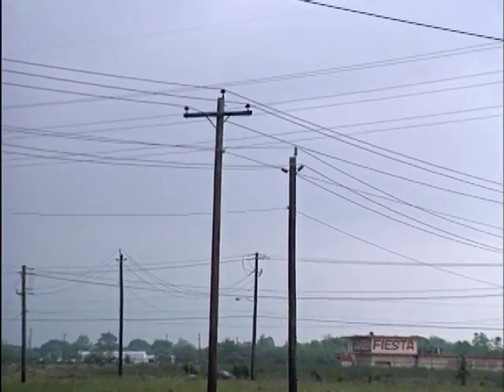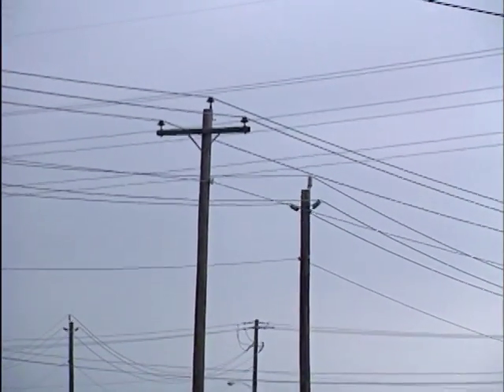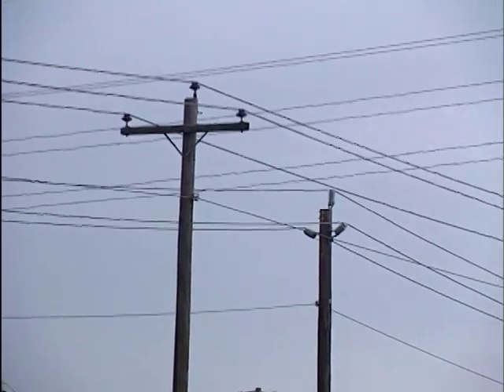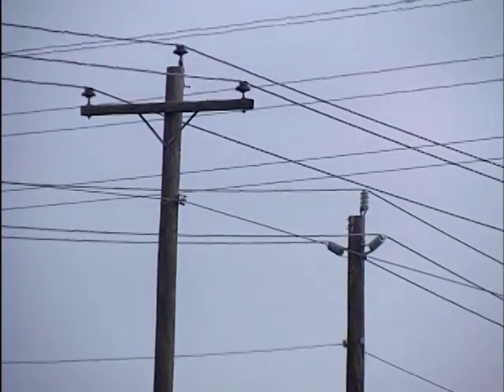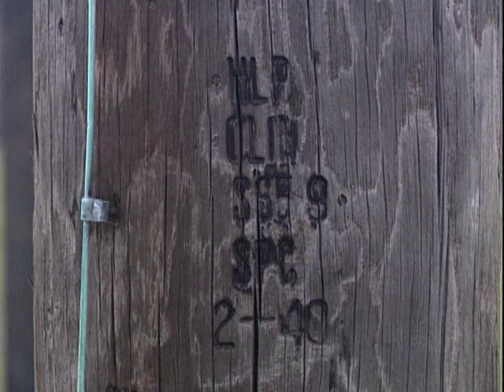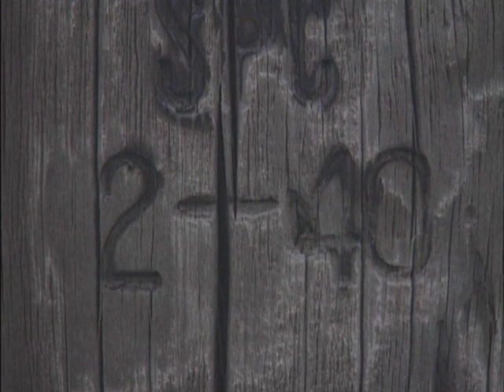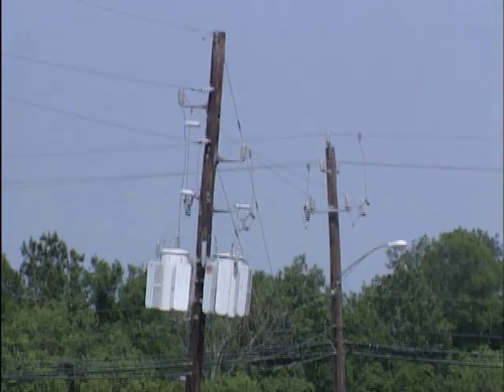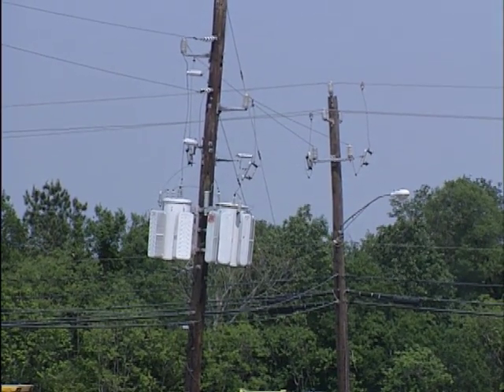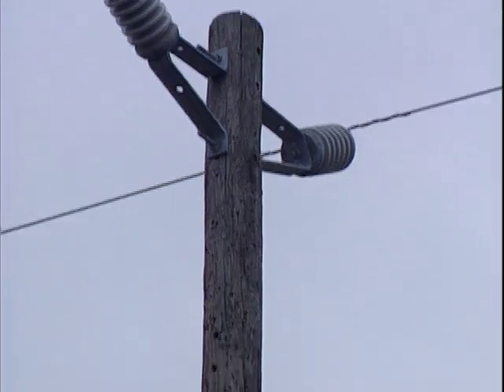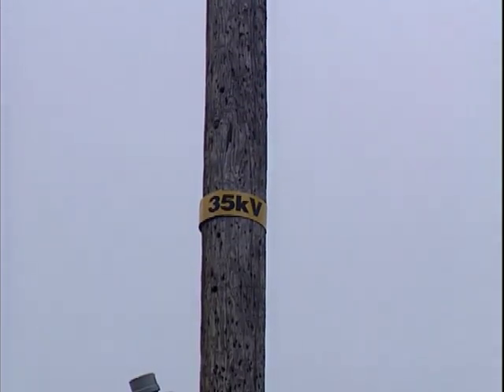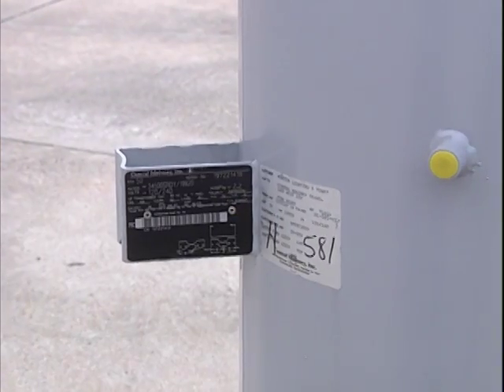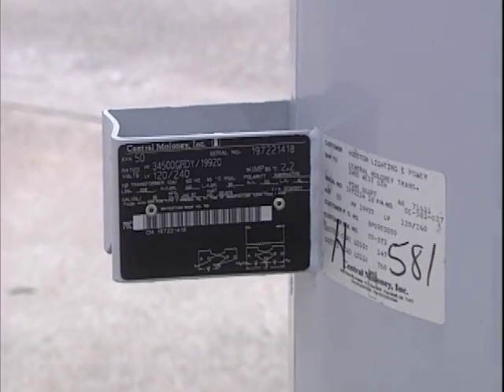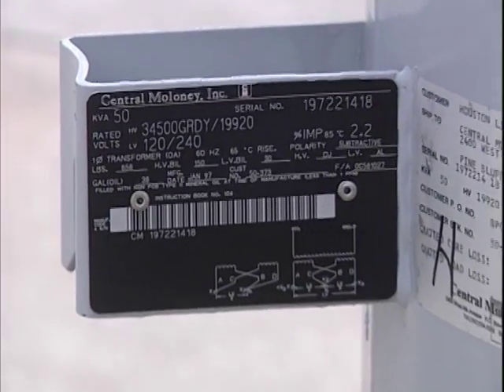The 12 kV system, 7,200 volts phase to ground, has a common neutral and can be framed with armed or armless construction. 12 kV pole heights are typically 40 to 45 feet. CenterPoint Energy makes extensive use of step-up and step-down transformers. In some instances, 12 kV framing is energized at a higher voltage. So, always refer to the nameplate on any associated equipment to determine voltage.